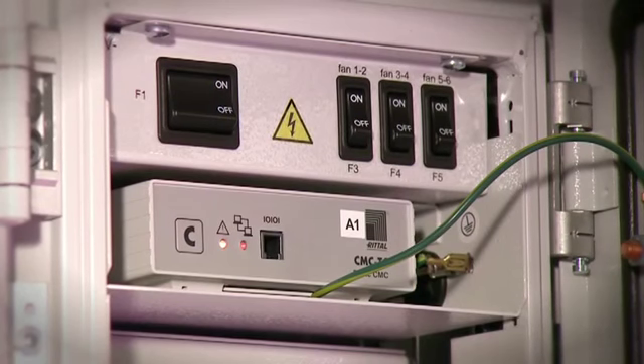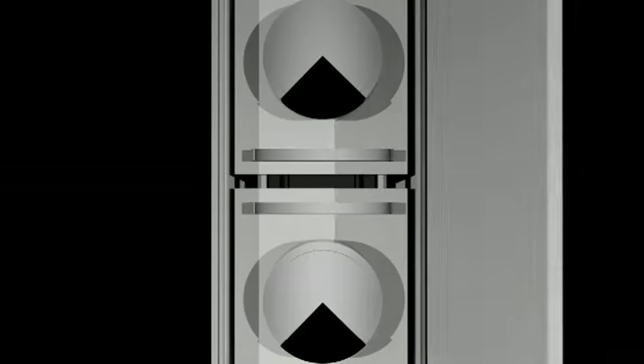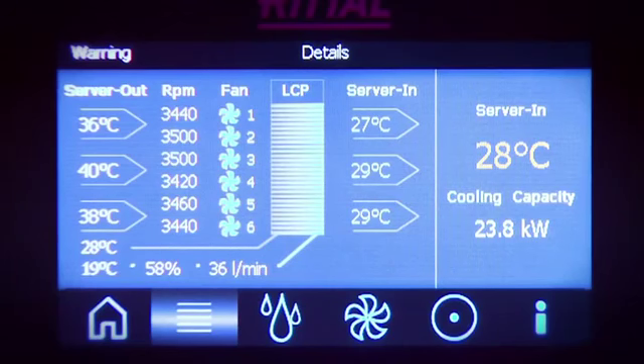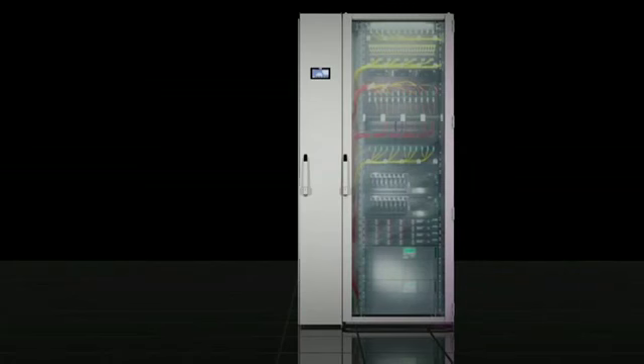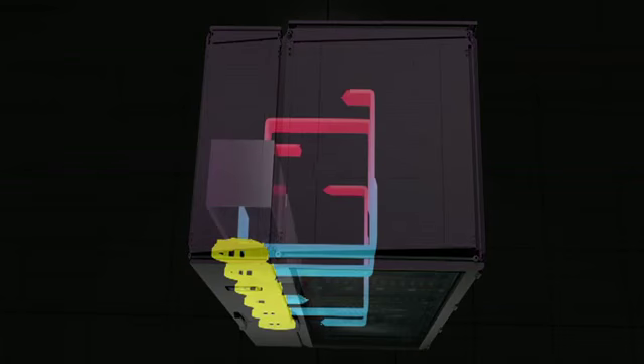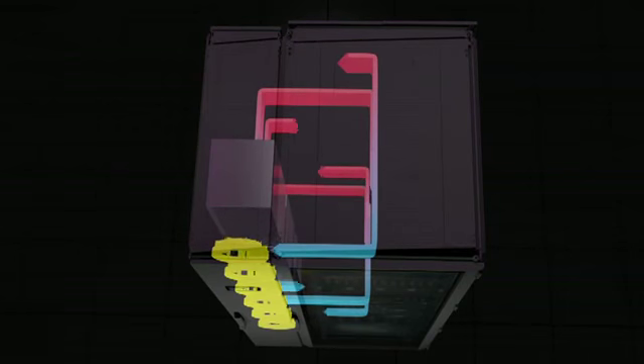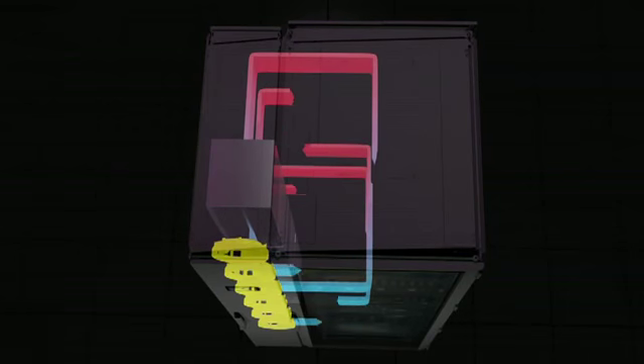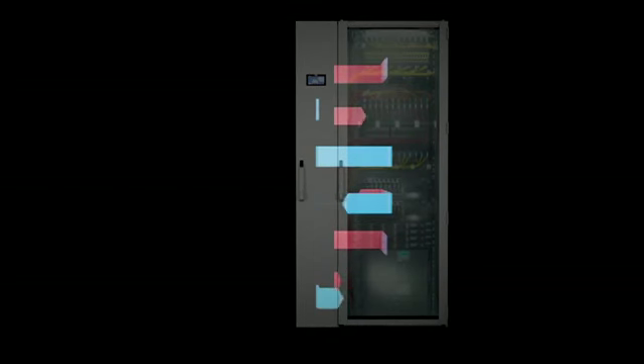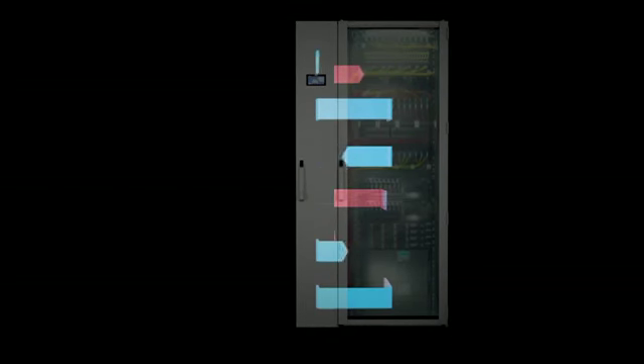Intelligent modules monitor the fans and the flow rates and are displayed on an optional touch-sensitive LCD screen on the front of the LCP Plus. The LCP Plus is connected to a standard 1200mm deep enclosure and pulls the hot air from the server exhaust and cools the air via the heat exchanger. It's been specifically designed to blow cool air across the whole height of the enclosure to ensure that there's no chance of having any hotspots developing.